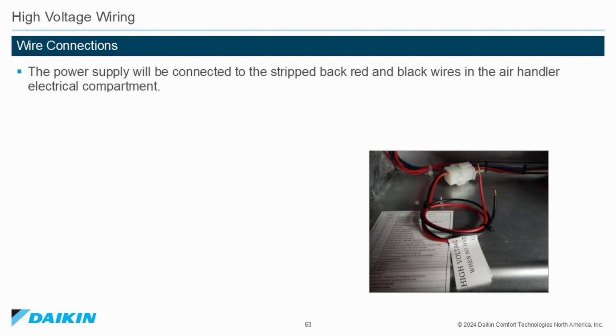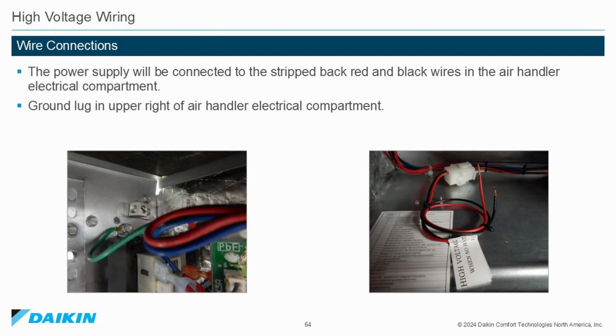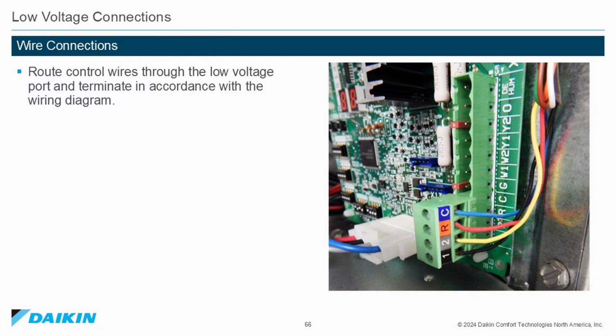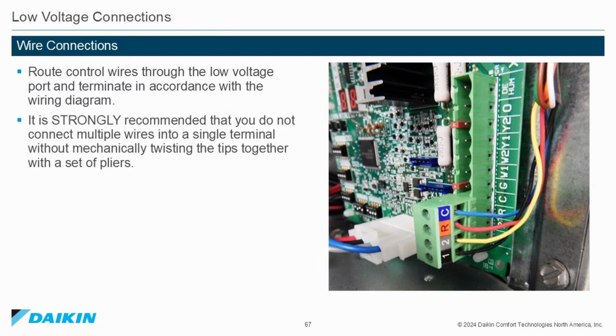High voltage wiring connections. The power supply will be connected to the red and the black wires that are already stripped in the Airhandler electrical compartment. The ground lug is located in the upper right-hand corner of the electrical compartment. Low voltage wire connections. Route the control wires through the low voltage port and terminate in accordance with the wiring diagram. It is strongly recommended that you do not connect multiple wires into a single terminal without mechanically twisting the tips together with a pair of pliers. Minimum wire size 18 gauge.